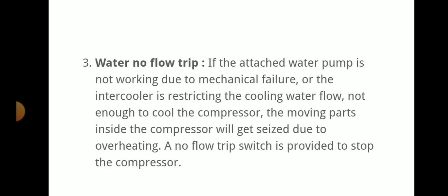Then water no flow trip. If the attached water pump is not working due to mechanical failure, or the intercooler is restricting the cooling water flow so that it is not enough to cool the compressor, the moving parts inside the compressor will get seized due to overheating. A no flow trip switch is provided to stop the compressor.